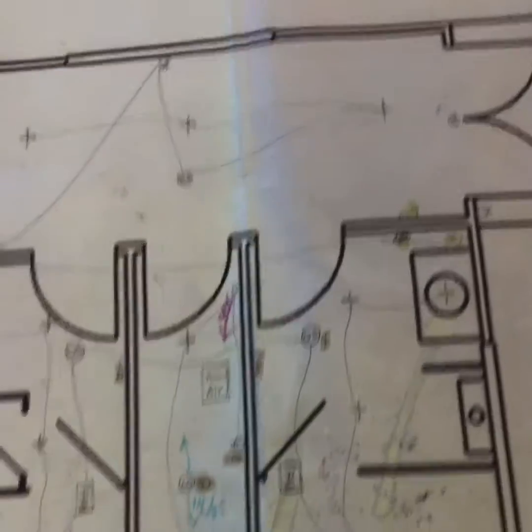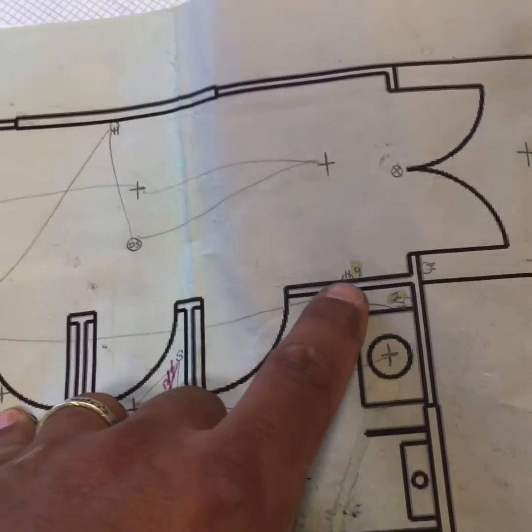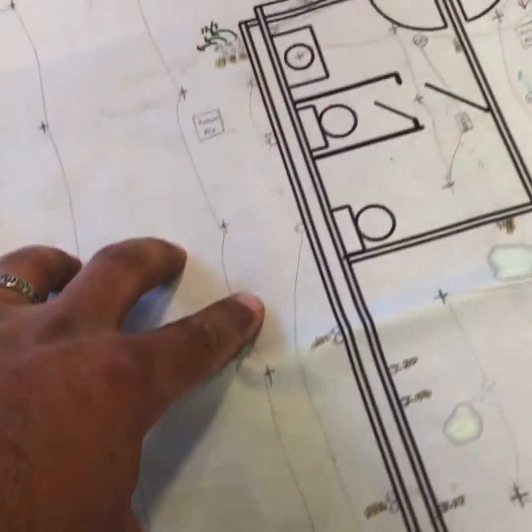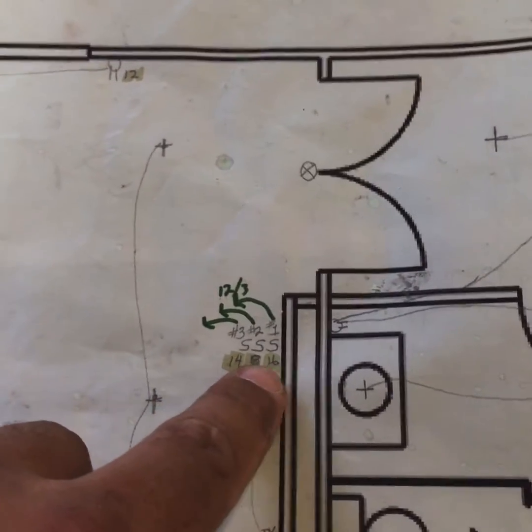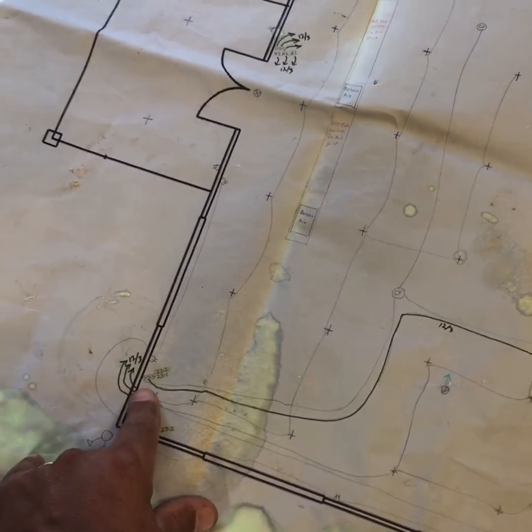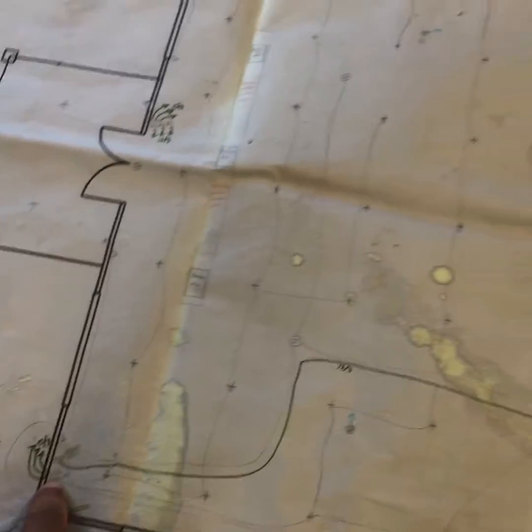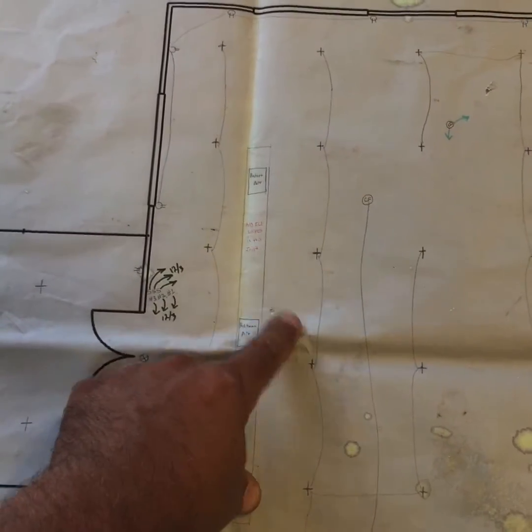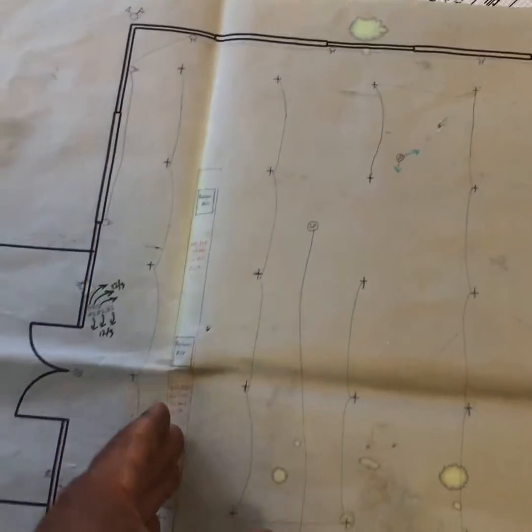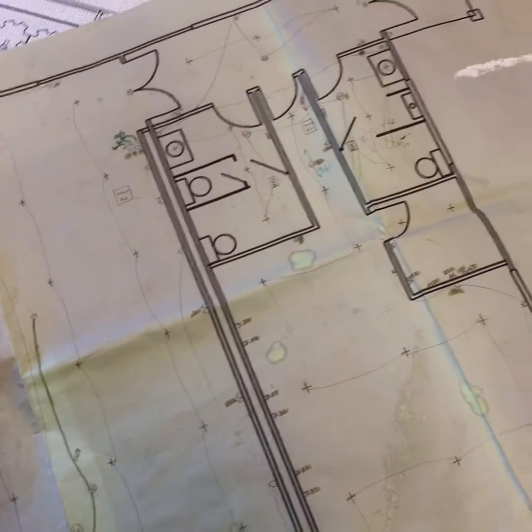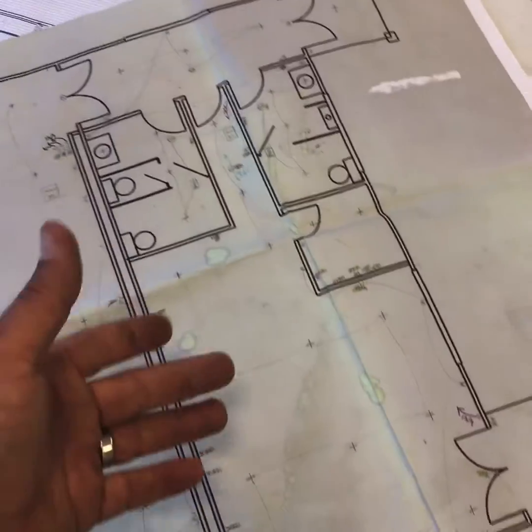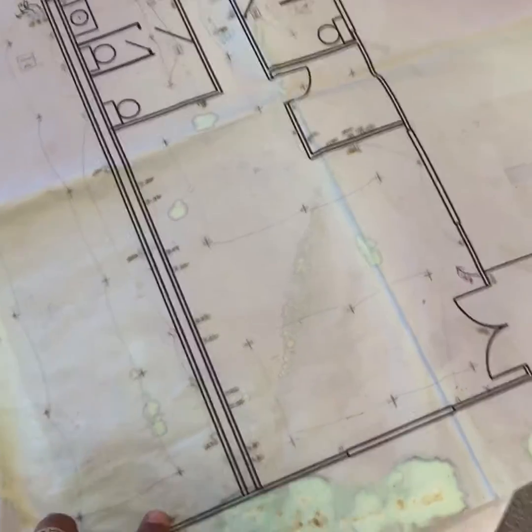So everything is essentially, this one here I didn't really draw out how to pull the wire for all the receptacles. I just basically, this is where a home run comes in, and they go accordingly. Got 3 circuits here, 1 circuit per bank of LEDs, halo lights. This I spent a little bit extra time on to make sure that I didn't overload the ampacity rating of these LED dimmer switches here. But that's it. And then right here, I went ahead and drew in some ductwork here, and this is to keep the guys from pulling wires through these ceiling joists, because this is all return duct here. And that's it. So that's just kind of an overview of the plan. Obviously, there's a ledger here that reminds me or tells the guys what circuit is what. That's it.